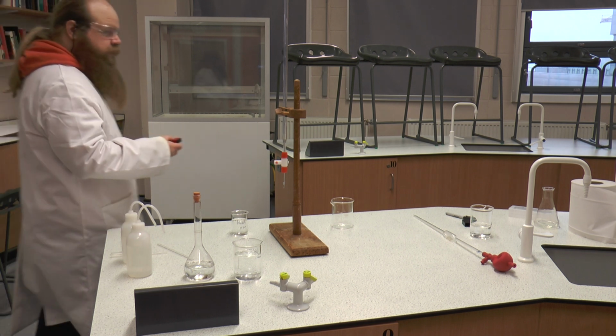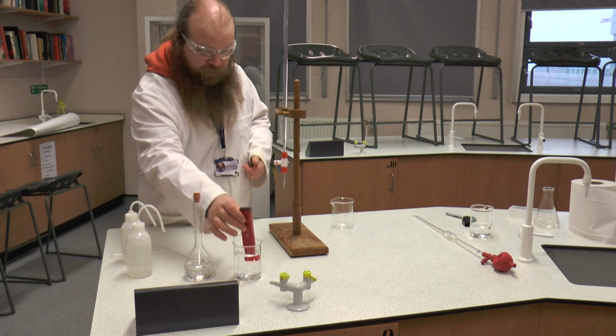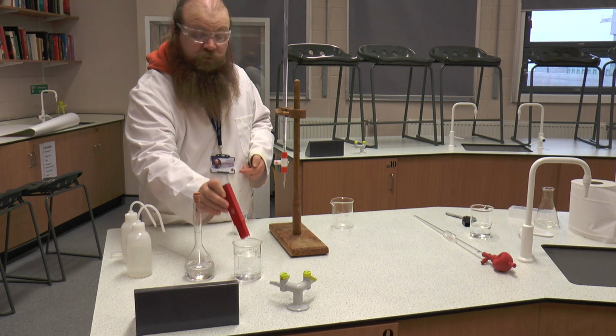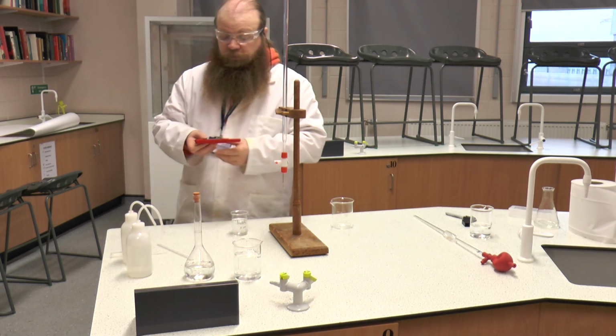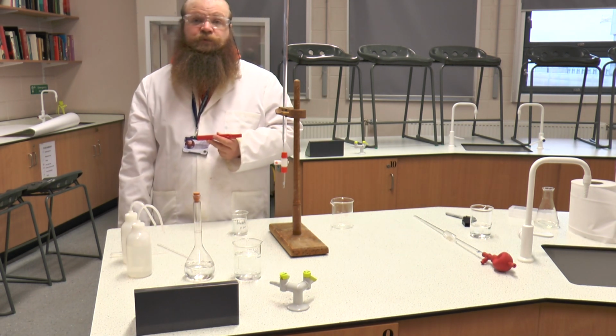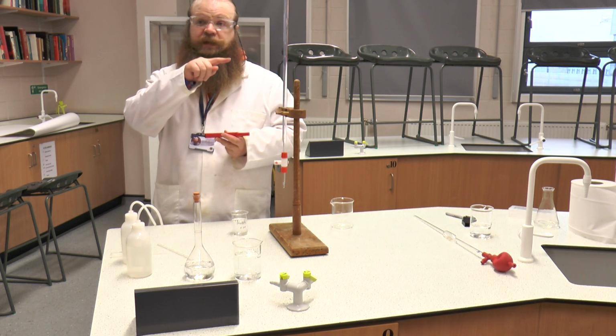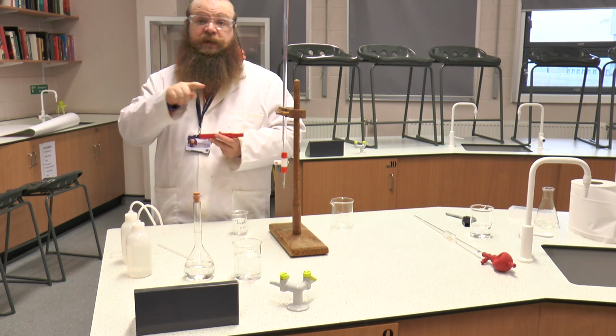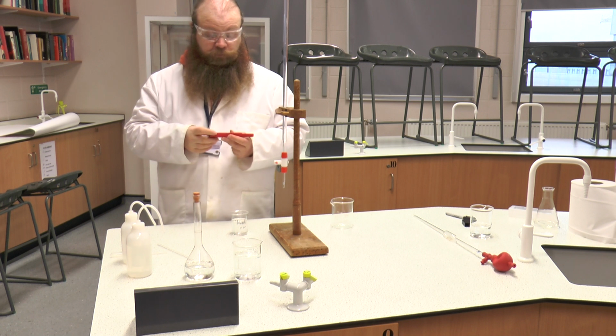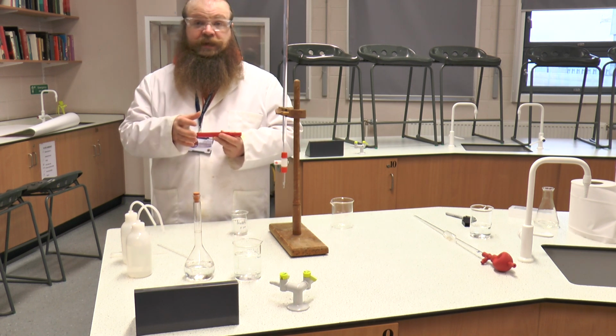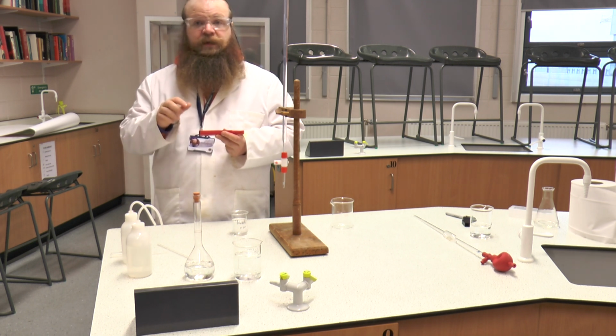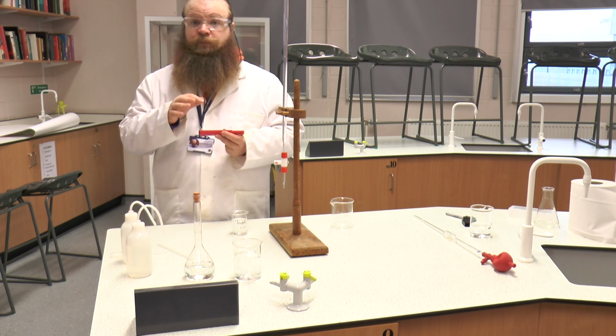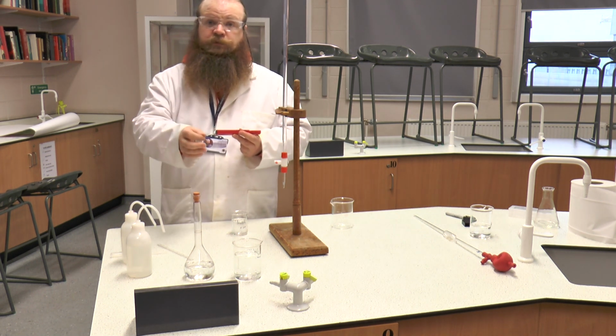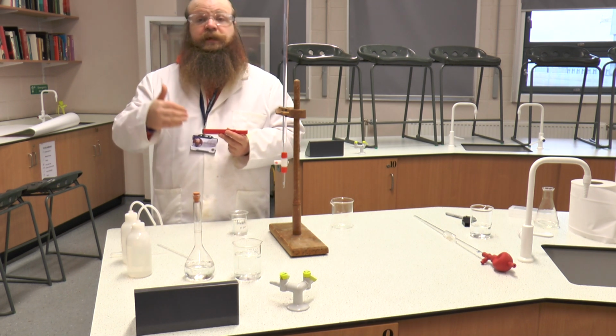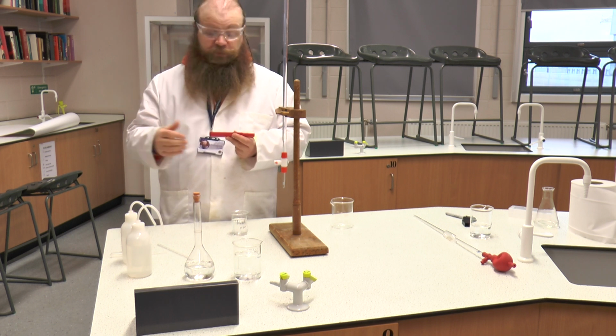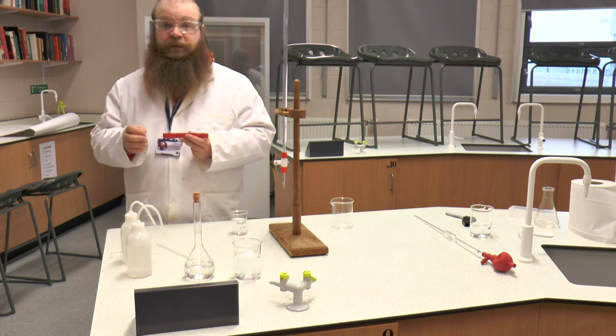Before use of this, we would calibrate our pH probe by placing it into solutions of known pH. One must be a pH 7 and then either a pH 4 or a pH 9, so that the device can then generate the pH curve for the solutions. So we will place it in the solution, press calibrate, and it will come up with calibrate 7, press it again and it will come up for calibrate 4 or calibrate 9, and we would place it in one solution, calibrate it, rinse it off with distilled water, take it and place it in a second solution and calibrate it for the second pH. And this is called a two-point calibration.